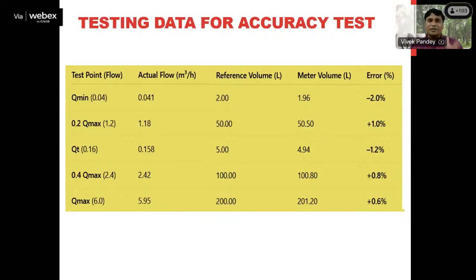Now, I'm just taking a small data set to make you understand how we will perform this exactly. Considering that flow chart I have just shown you, suppose we are performing a test of the gas meter at a minimum flow rate, say 0.04 meter cube per hour. After running the gas at this minimum flow rate, the reference gas meter is indicating, suppose, 2 liters. However, our gas meter is indicating 1.96 liters. So we can compare these two values: measured value minus reference value, upon reference value, into 100. We will calculate the percentage error, and suppose that percentage error comes out as minus 2% in this case. Fine. And similarly, we will perform the test at other flow rates: 0.2 times Q maximum, then Q transitional, then 0.4 times Q maximum, and then Q maximum.